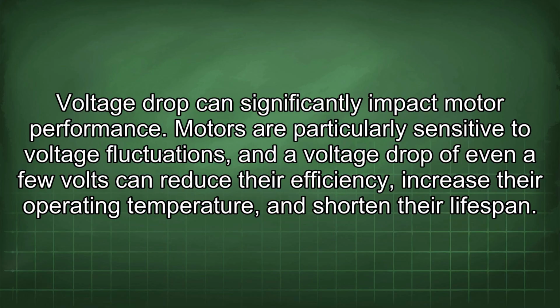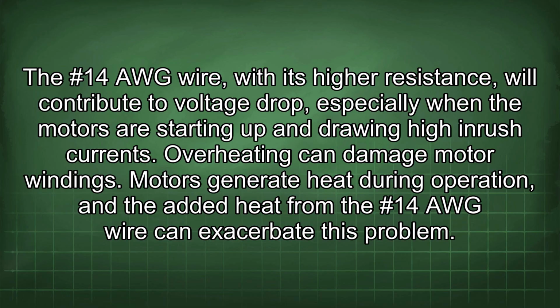Voltage drop can significantly impact motor performance. Motors are particularly sensitive to voltage fluctuations, and a voltage drop of even a few volts can reduce their efficiency, increase their operating temperature, and shorten their lifespan. The #14 AWG wire, with its higher resistance, will contribute to voltage drop, especially when the motors are starting up and drawing high inrush currents.